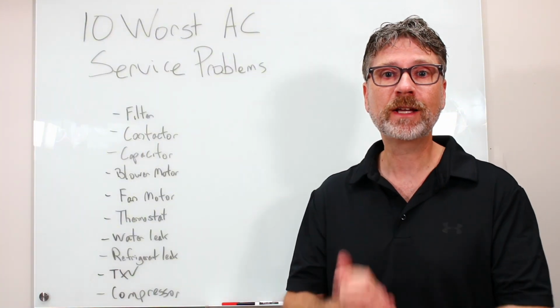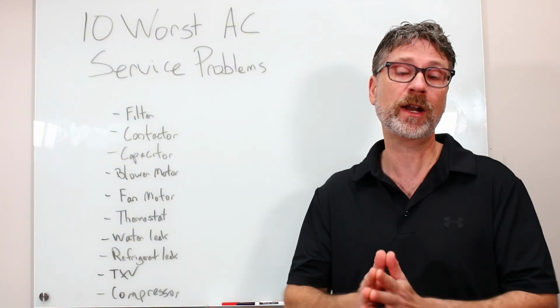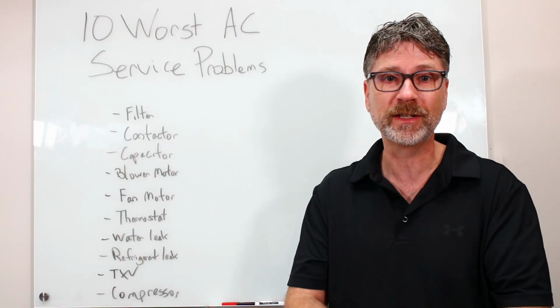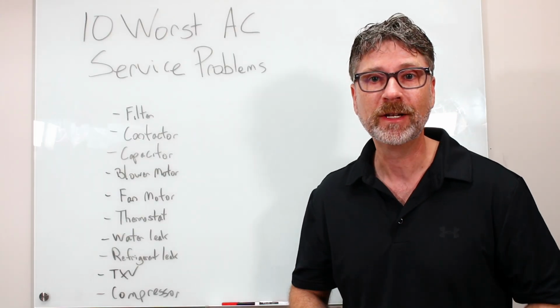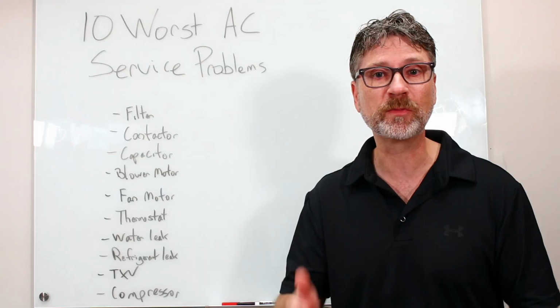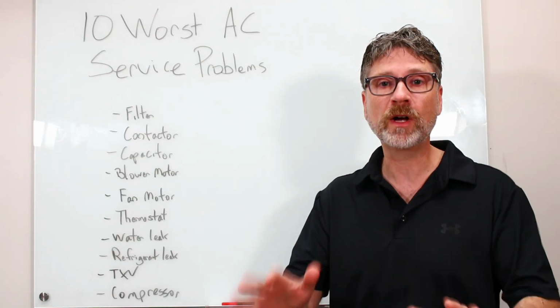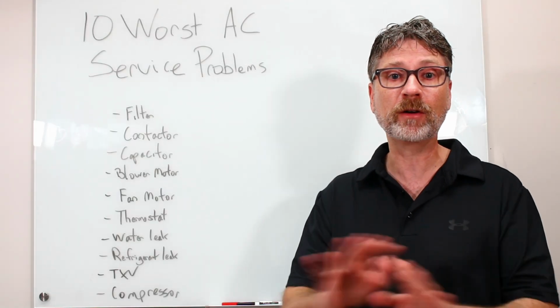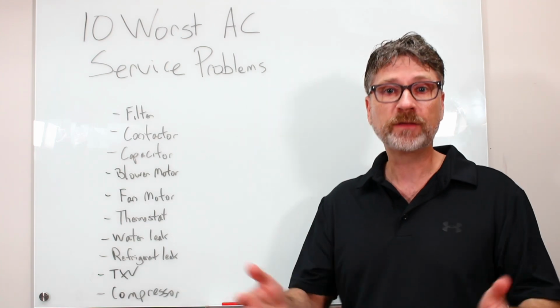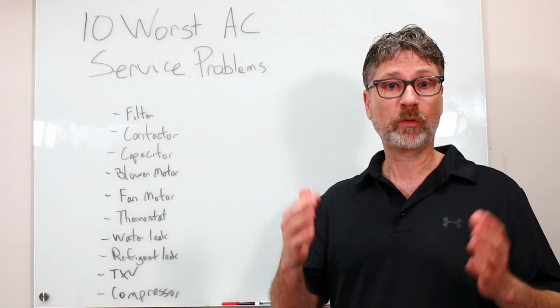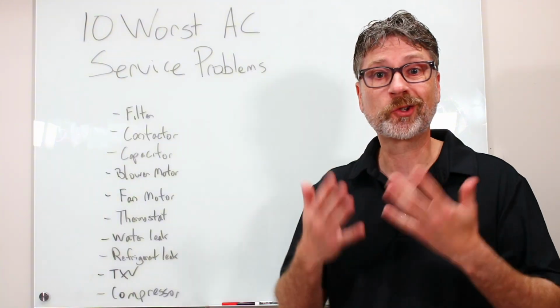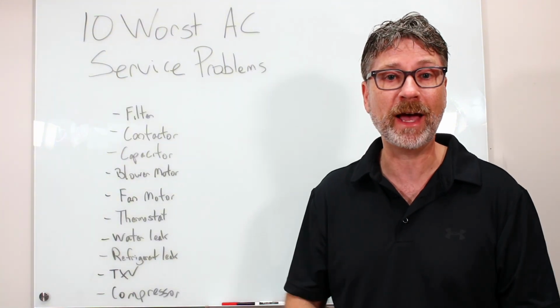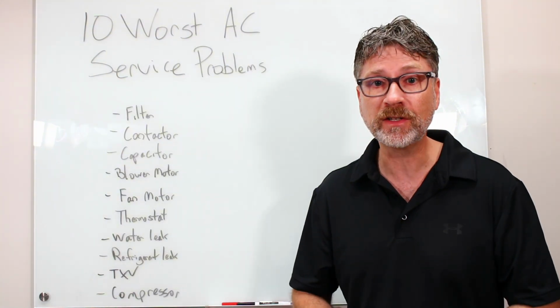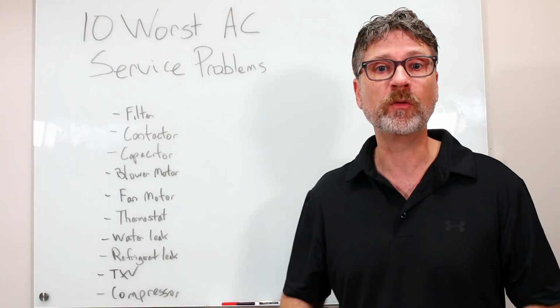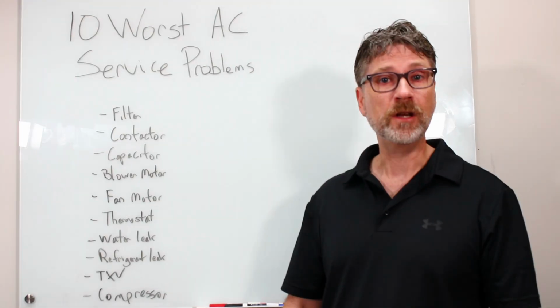The most common thing that we see, and ironically one of the most preventable things, is a plugged filter. We saw a mini split system just this week, for example, that had so much drywall dust on it that it barely functioned at all. Plugged filters will cut your airflow, raise the temperature in your house, shorten the life of your system. It's just bad. Replace your filters as often as they get dirty, which could be every 1 to 3 months in most homes.